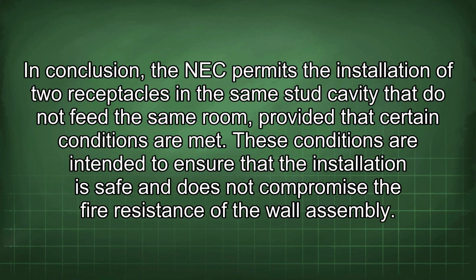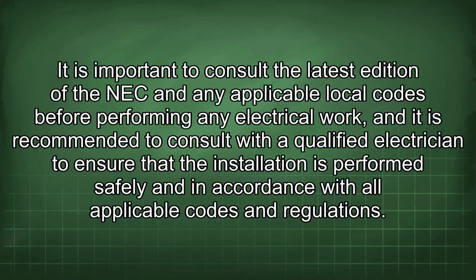In conclusion, the NEC permits the installation of two receptacles in the same stud cavity that do not feed the same room, provided that certain conditions are met. These conditions are intended to ensure that the installation is safe and does not compromise the fire resistance of the wall assembly. It is important to consult the latest edition of the NEC and any applicable local codes before performing any electrical work, and it is recommended to consult with a qualified electrician to ensure that the installation is performed safely and in accordance with all applicable codes and regulations.